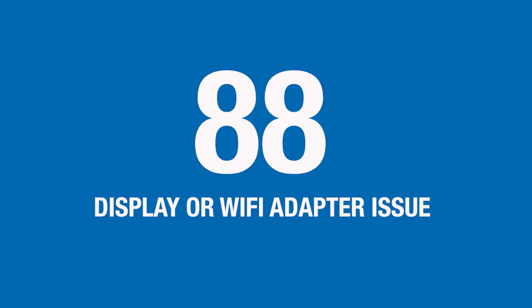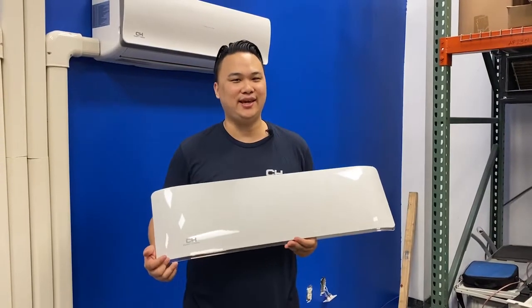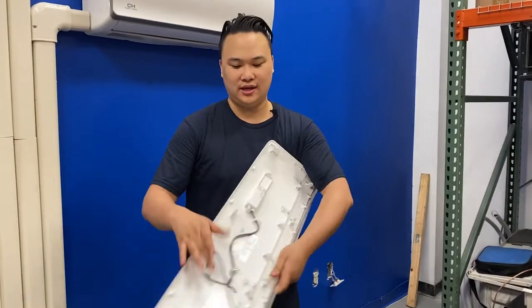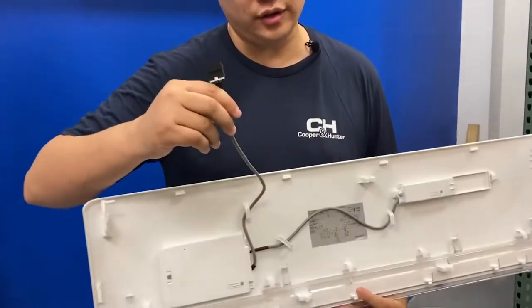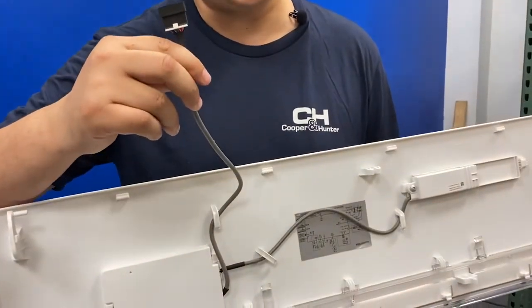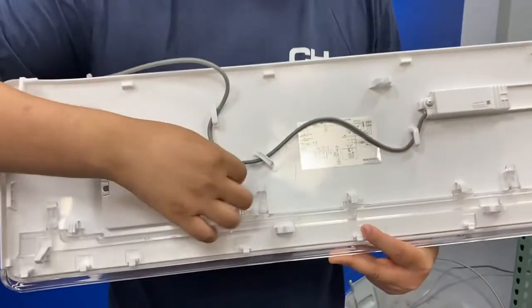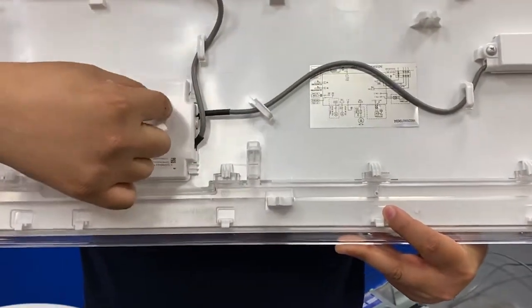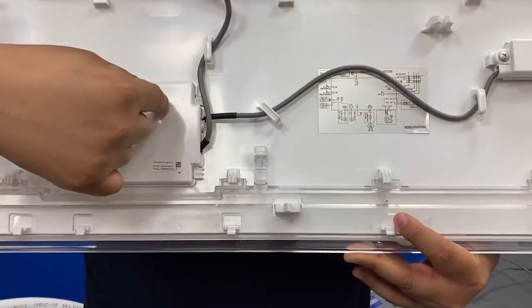If your unit is showing a solid non-flashing 88, it's one of two things. Either the connection point to the indoor main control board is not seated properly, or the Wi-Fi dongle adapter is not seated properly onto the display board.